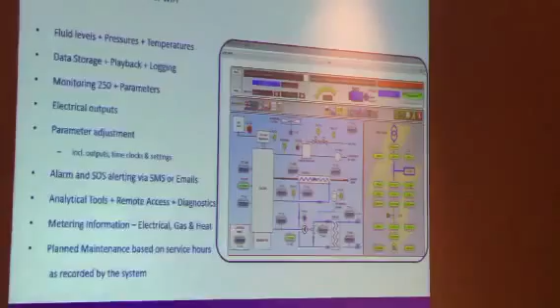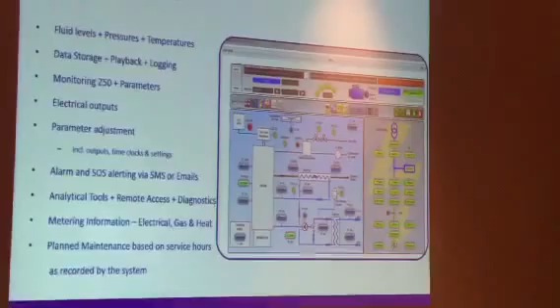We've also got metering information, and with that, planned maintenance. We base all our planned maintenance on hours run - typically the service interval would be at 1600 hours, and the onboard metering counts that down, giving us a warning before servicing needs to take place. We can also use it for overhauls, planning for top-end and major overhauls - since it's an engine, it will need new cylinder heads, pistons and internal components, and we put all that into the database so it can provide warnings for that too.